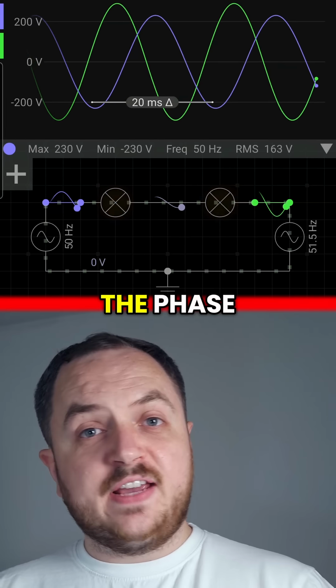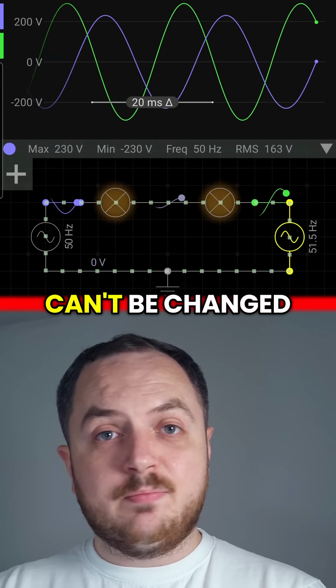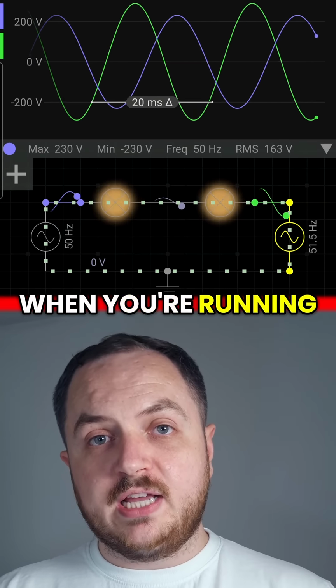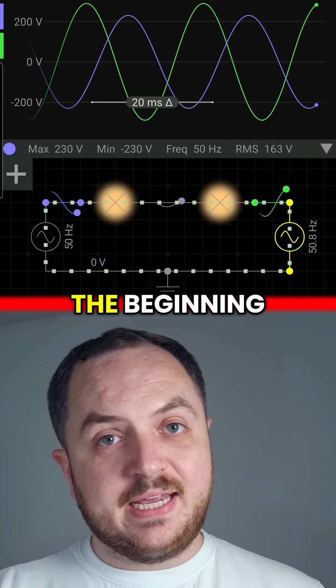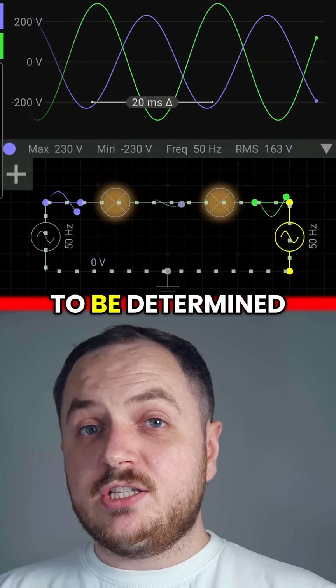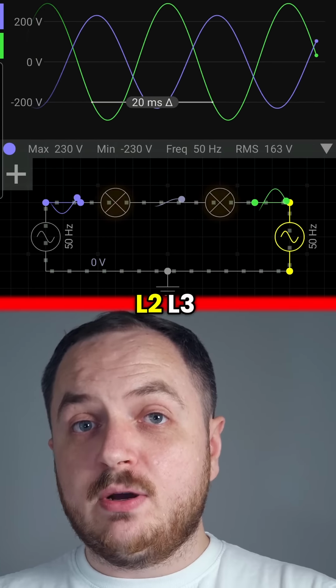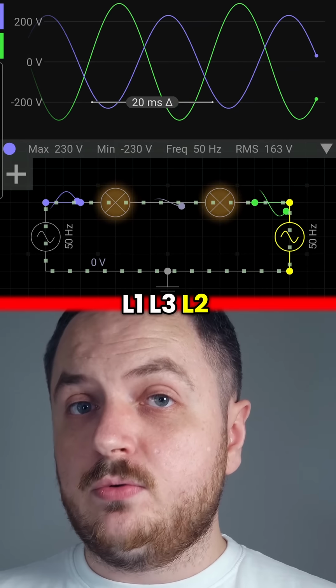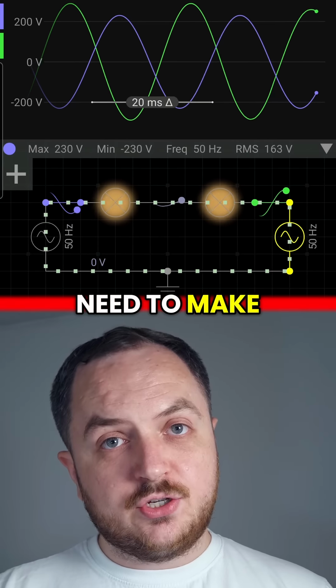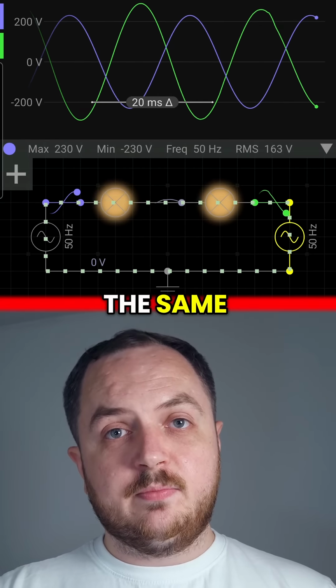So let's talk about the phase sequence then. This is something that can't be changed or altered when you're running that generator. It has to be right from the beginning. So firstly, the main supply needs to be determined what it is. Is it L1, L2, L3, or is it L1, L3, L2? Once you've found that out, you just need to make sure your generator is operating in the same phase sequence.